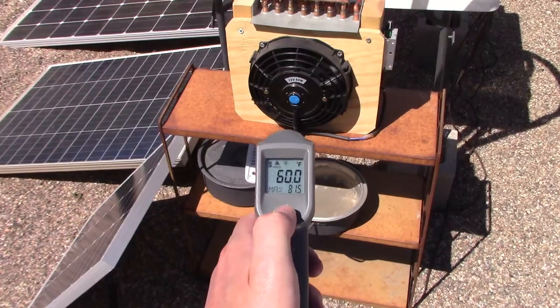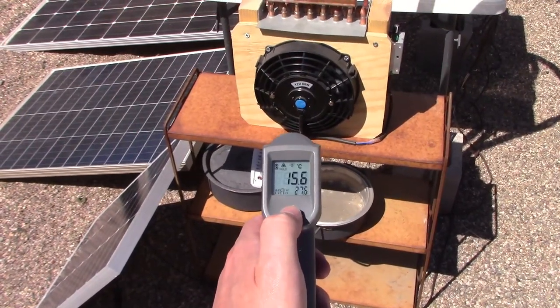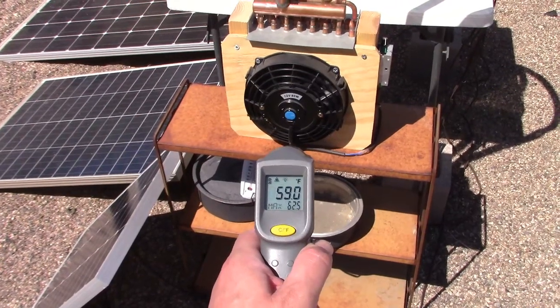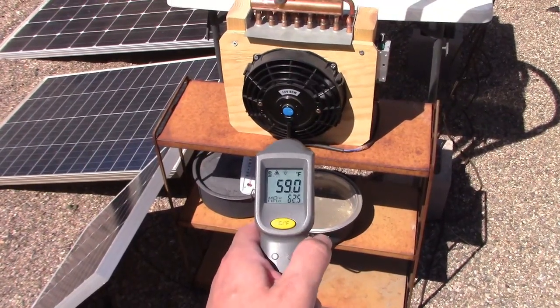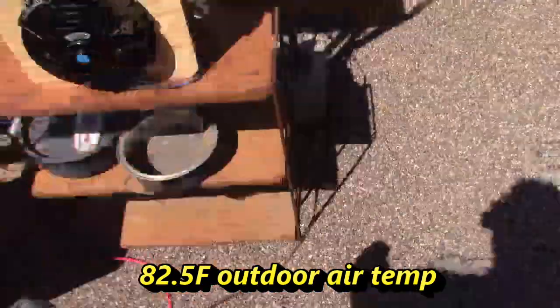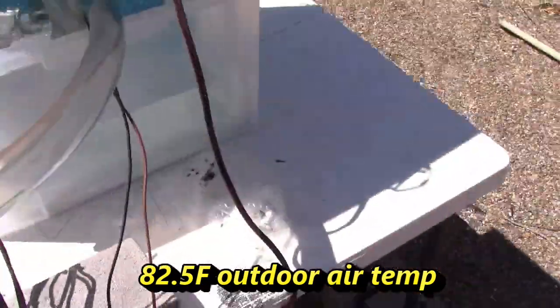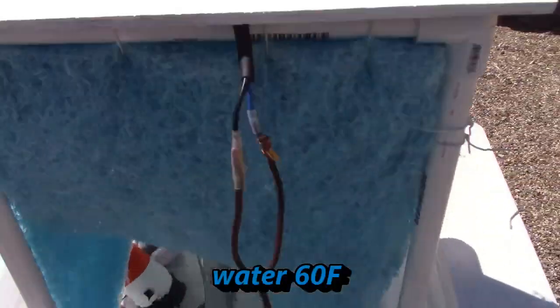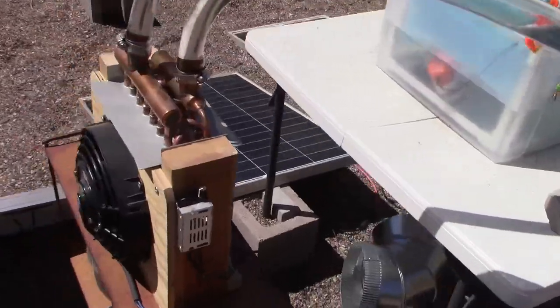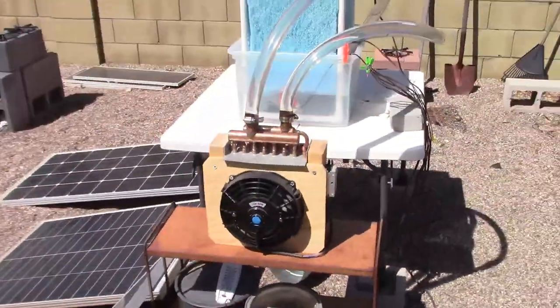Again, there's your unit temps, about 60F, 15.6 Celsius. 59F, 15 Celsius. That's awesome, I just can't believe it. It's staying exactly the same temperature as the water. It couldn't be working better, it's working absolutely awesome. Indirect evap cooling.